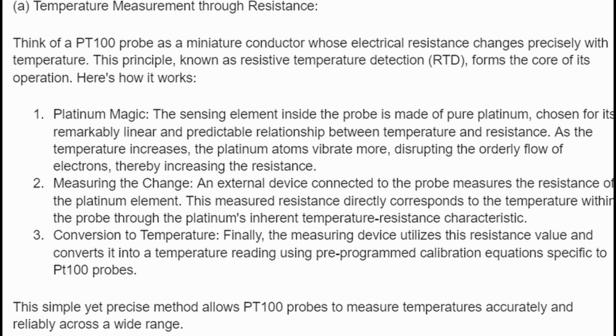A. Temperature measurement through resistance. Think of a PT100 probe as a miniature conductor whose electrical resistance changes precisely with temperature. This principle, known as resistive temperature detection, RTD, forms the core of its operation. Here's how it works. 1.